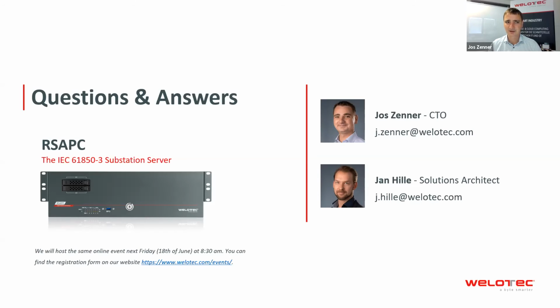I was talking to ETAP recently. They have one of those solutions. So converting protocols is not a problem. They can run on our platform without any issue. Usually you speak IEC 61850 within the substation, and then you go northbound with DNP3, or in Europe you will take IEC 104.